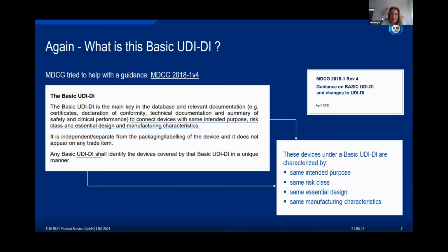It is, let's say, an identifier for manufacturer unique devices. So that means the basic UDI-DI is characterized by the same intended purpose. Intended purpose, I say it clearly. So as I mentioned before, intended purpose solely, the same risk class, I mean, that is clear, the same essential design and the same manufacturing characteristics.